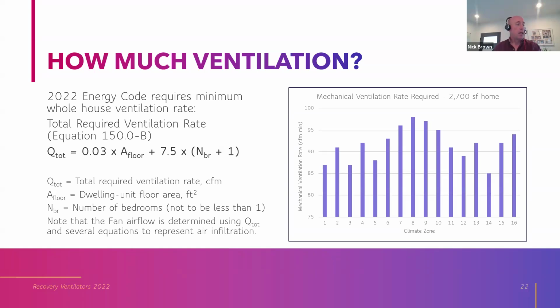You'd be correct. The reason is our climate zones all have different assumptions on wind speed, and wind speed affects infiltration through the envelope, and infiltration through the envelope is outside air. So the more infiltration you have, the less airflow the fan needs to do. So basically these climate zones with lower CFM required for the fan have higher wind speed on average in the assumptions. But look at the numbers.